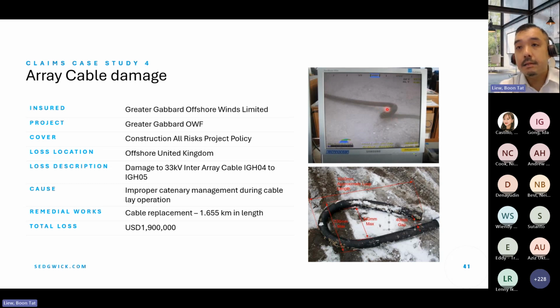This causes issues. First, cables during installation have manufacturers' guidelines that they're not supposed to exceed a certain bend radius. If they do, that actually affects their working life and also creates potential warranty issues. However, another issue when it comes to loops like this is understanding how these cables are actually made.